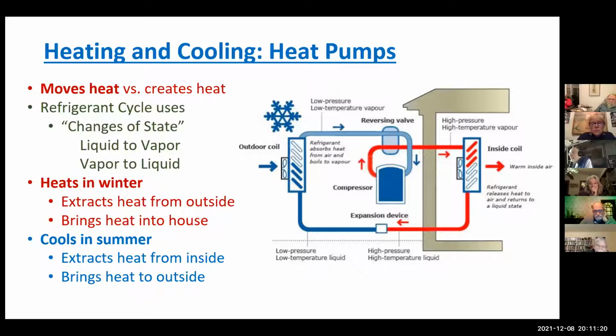And there's a reversing valve, which makes the heat pump more than just a one-way system. So you have an air conditioner, perhaps, that's a one-way system. The refrigerator is a one-way system. The heat pump has a reversing valve, and it allows the system to work the other way around, so you can now take heat out of your house in the summer and put it to the outside.